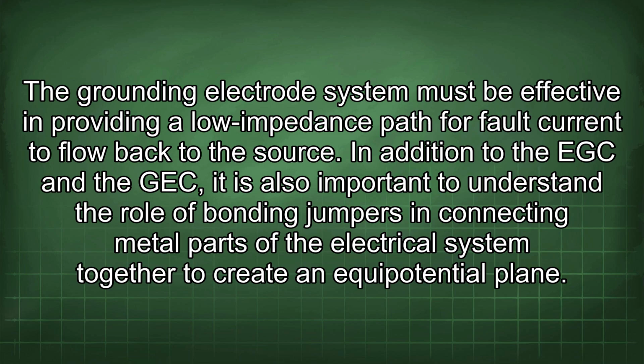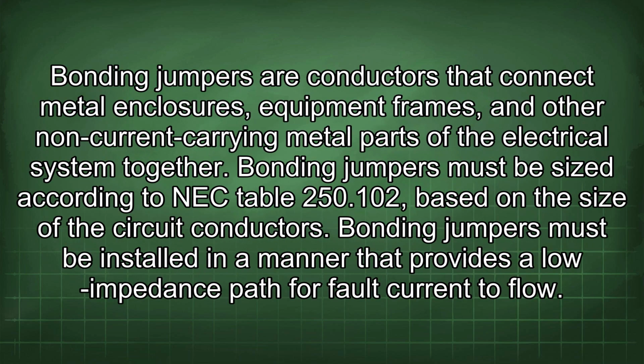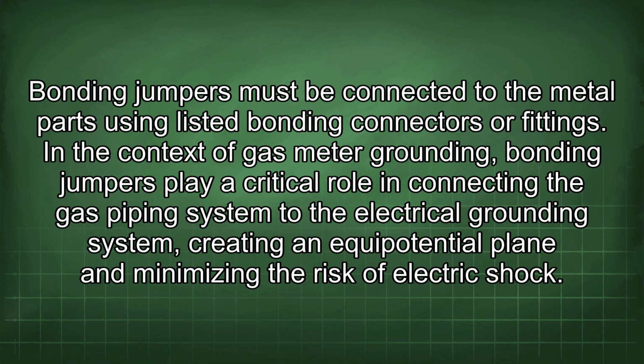In addition to the EGC and the GEC, it is also important to understand the role of bonding jumpers in connecting metal parts of the electrical system together to create an equipotential plane. Bonding jumpers are conductors that connect metal enclosures, equipment frames, and other non-current carrying metal parts of the electrical system together. Bonding jumpers must be sized according to NEC Table 250.102 based on the size of the circuit conductors. Bonding jumpers must be installed in a manner that provides a low impedance path for fault current to flow. Bonding jumpers must be connected to the metal parts using listed bonding connectors or fittings.